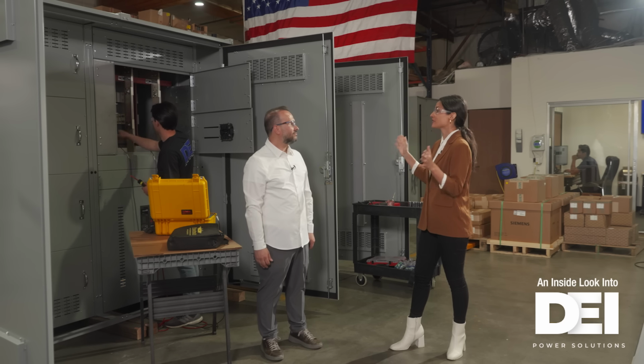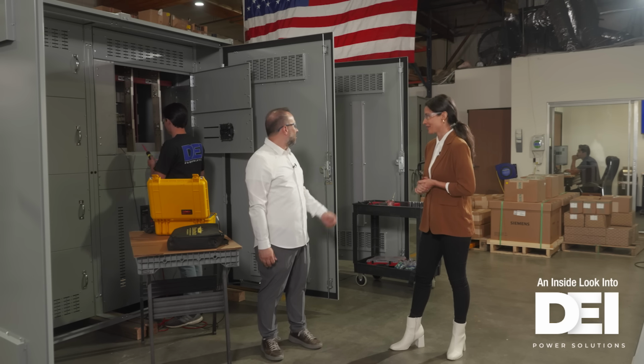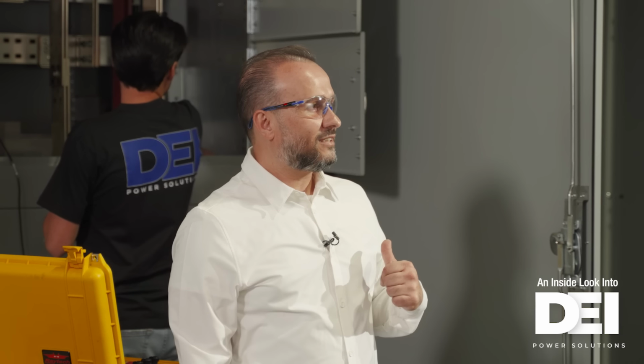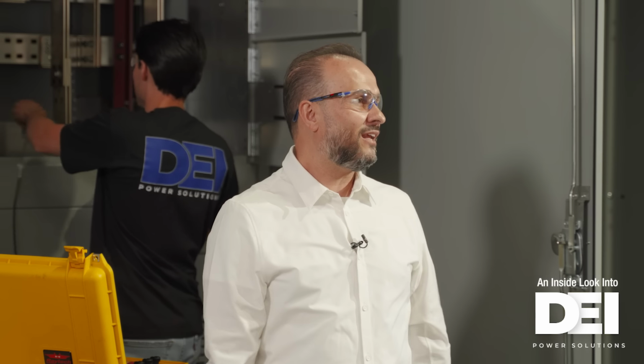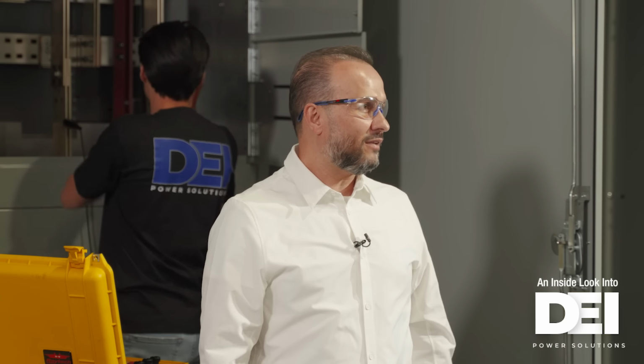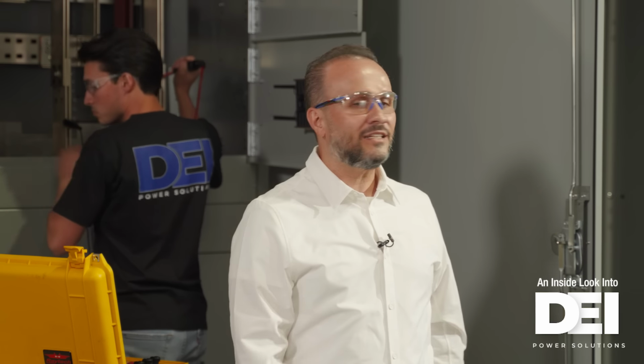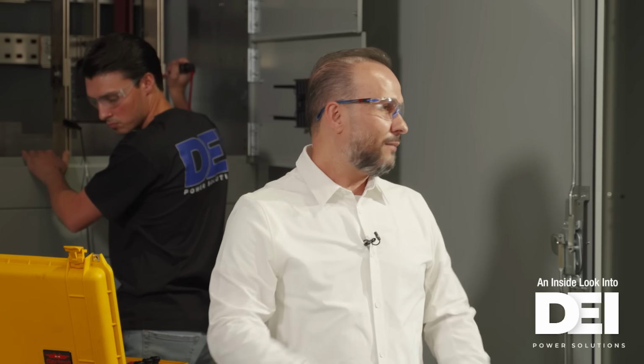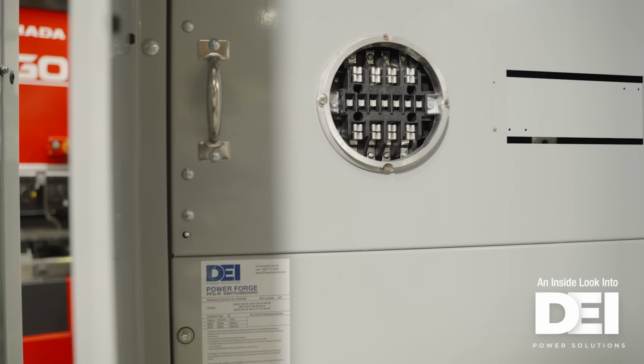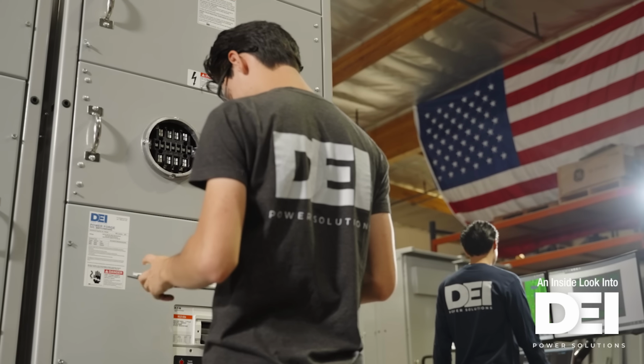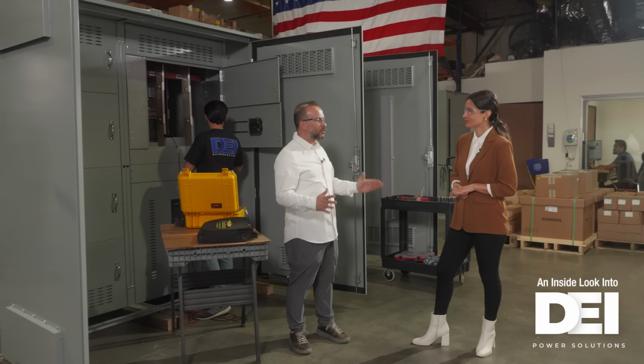So it looks like we're here at the final stages. Why don't you walk us through what's happening? They're doing a contact resistance test. That's one of the tests we do prior to any panel that leaves our facility. It goes through an intensive quality check. We want to make sure the customer is getting exactly what he needs and everything is testing out the way it needs to. Every circuit breaker is tested, ground bond is tested, high pot. We also do all types of ground fault testing prior to the breaker leaving our facility. There's an intensive 2 or 3 days needed for this quality check.